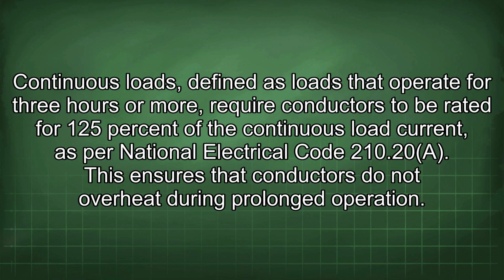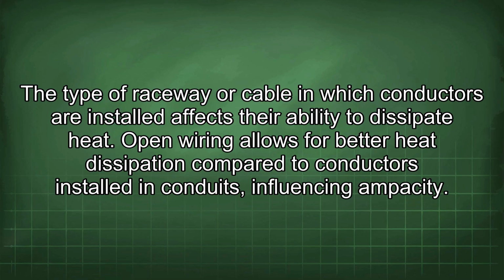Continuous loads, defined as loads that operate for 3 hours or more, require conductors to be rated for 125% of the continuous load current as per National Electrical Code 210.20(A). This ensures that conductors do not overheat during prolonged operation. The type of raceway or cable in which conductors are installed affects their ability to dissipate heat. Open wiring allows for better heat dissipation compared to conductors installed in conduits, influencing ampacity.